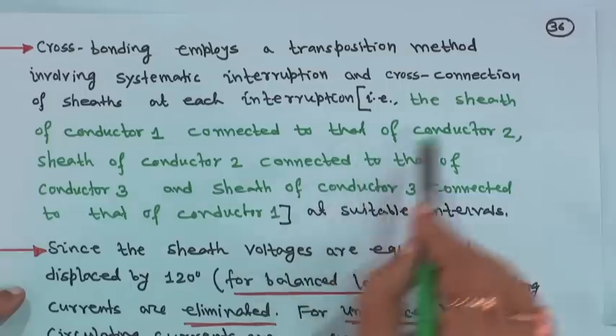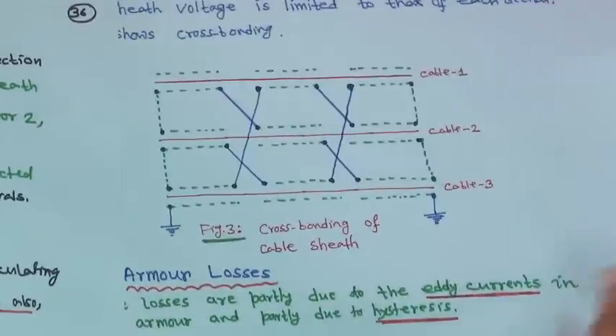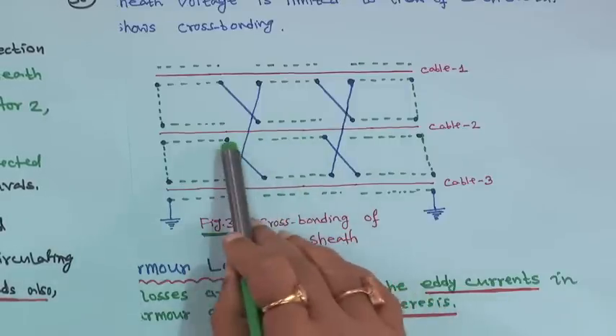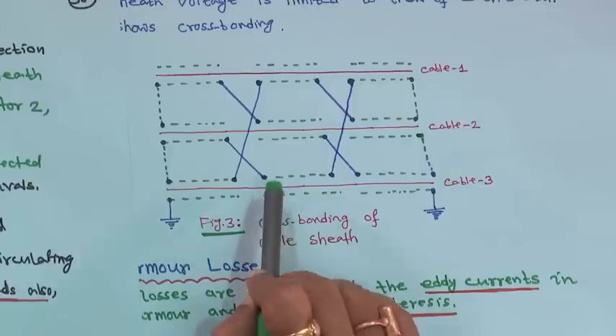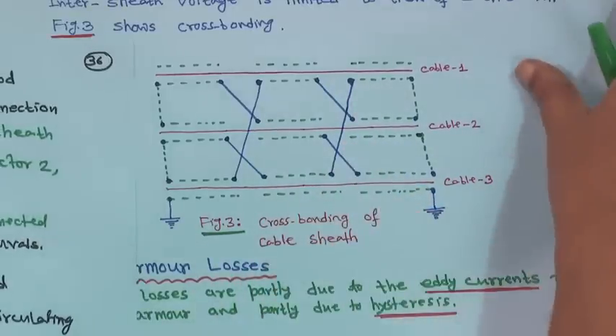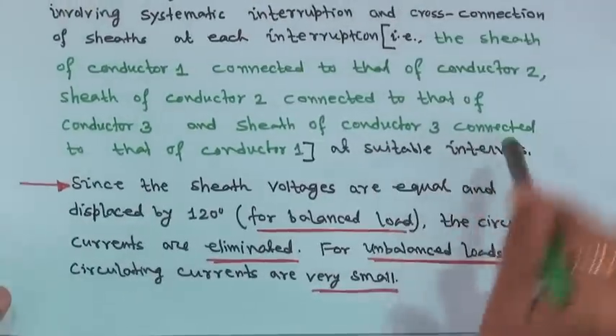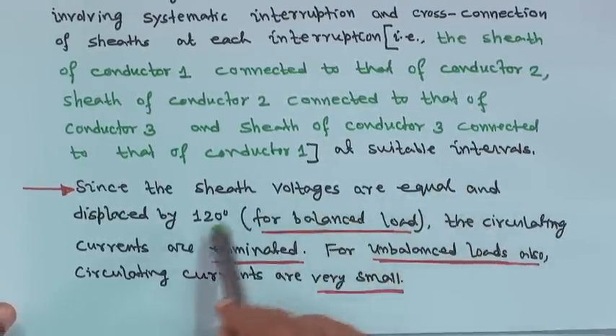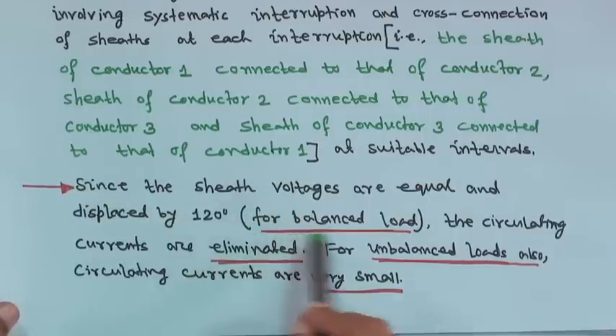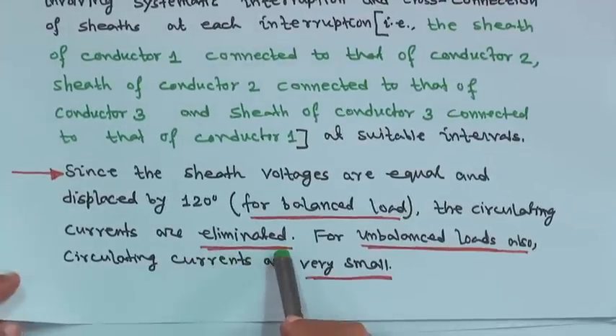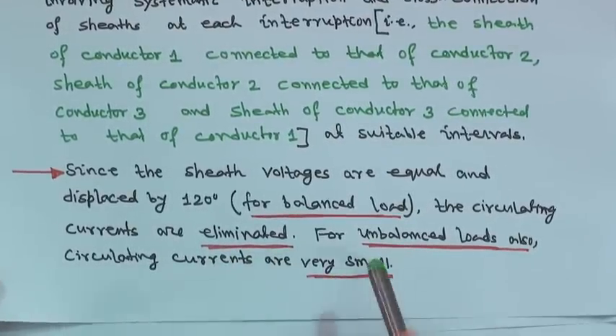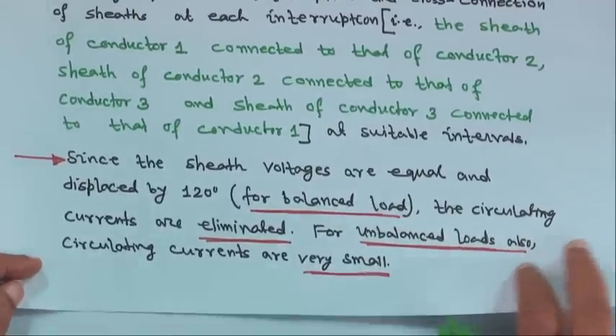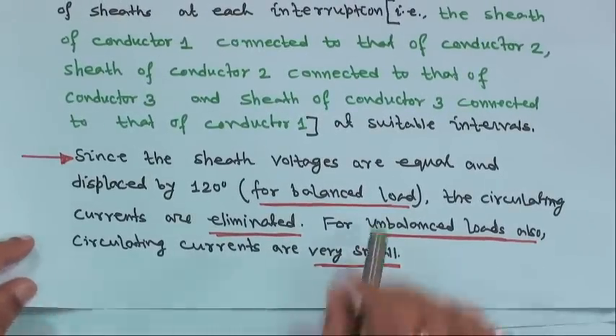The sheath of conductor 1 is connected to conductor 2's sheath, the sheath of conductor 2 is connected to conductor 3's sheath, and the sheath of conductor 3 is connected to conductor 1's sheath — at suitable intervals. This way circulating current can be minimized. Since the sheath voltages are equal and displaced by 120 degrees for balanced load, circulating currents are eliminated. For unbalanced load also, circulating currents are very small, particularly for 11 kV distribution cables.